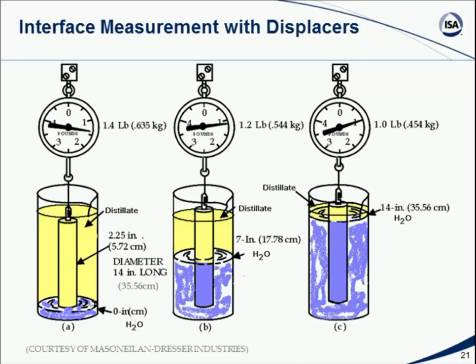But as the water level in the tank rises, again, the water will be pushing against the displacer, and the density of water is different from the density of the distillate. Obviously, its density is greater, which is why it's sunk down below. As the water level rises, we will again see the weight of the displacer change. So let's just cut to the chase. When the water level is all the way up to 14 inches, meaning pretty much the tank is full of nothing but water, the hanging weight for the displacer is now 1 pound. When there was no water, it was 1.4 pounds. So now we can measure the water in the bottom of the tank using a displacer that's put down there, to know the level of water in the tank from no water all the way up to 14 inches by seeing the weight of the displacer change between 1.4 pounds and 1.0 pounds.